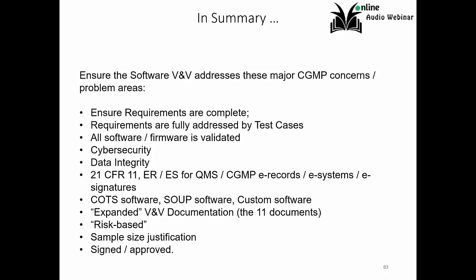And then all your data should be under the principles of data integrity and writing down and recording this information. Cybersecurity methods have to be addressed if necessary. Part 11 has to be addressed where necessary. Commercial off-the-shelf software, there's some data you won't be able to gather, and you have to indicate that in your documentation. The other area where you include that is SOUP, software of unknown provenance. You have to make up what is unknown, what is missing, before you can use that software by replicating the testing.